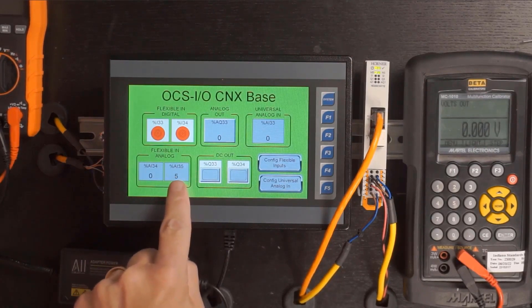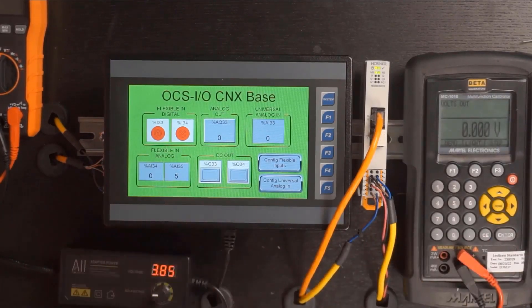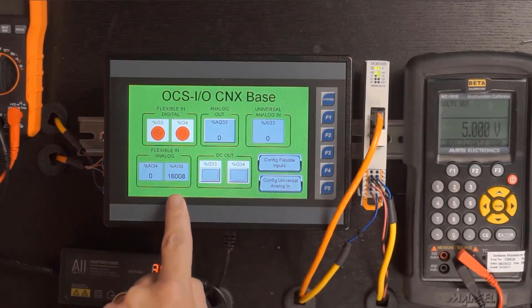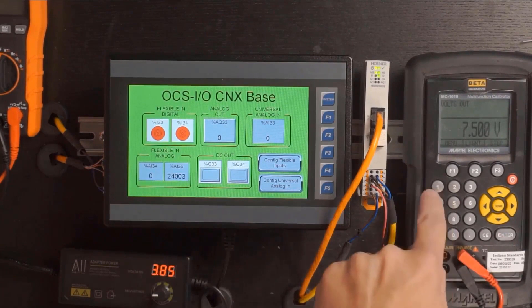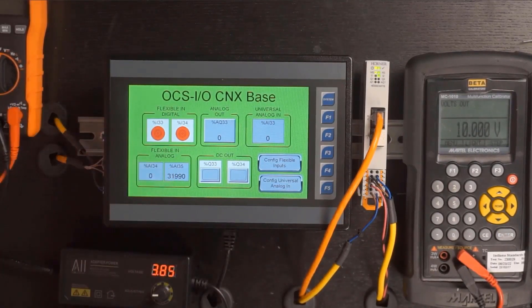Now we look at the second flexible input configured for analog mode in 0 to 10V. On our simulator at 0V, we're at about 5 counts due to 15-bit resolution. At 5V we're around mid-range at 16,000. At 7.5V we're up around 24,000 counts, and at full scale we reach near 32,000. So we configured the first flexible input as a digital with custom thresholds, and the second as an analog.